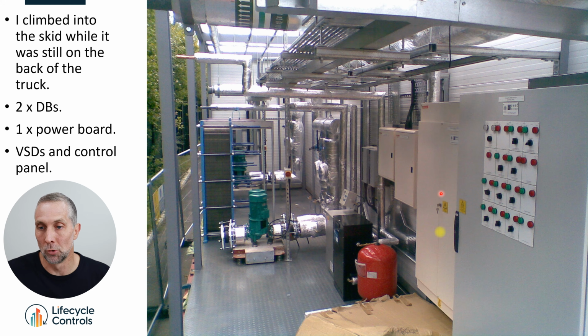Here's a big power distribution board. He has 2 distribution boards, 2 Danfoss variable speed drives at the back there, a pressurization unit, some pumps, heat exchangers, lagging, everything's down here. There's some power wiring. We never ran the instrumentation cabling. The next time I did this, I would have tried to work out how to do all the instrumentation cabling, and I would have had a small control panel on each of the 4 skids so I could completely wire the power and controls in one quadrant and not have cables cross between the 4 skids.